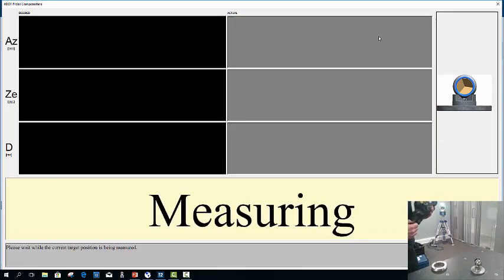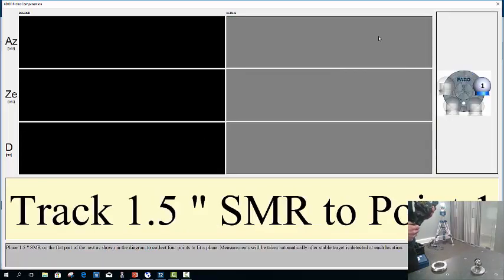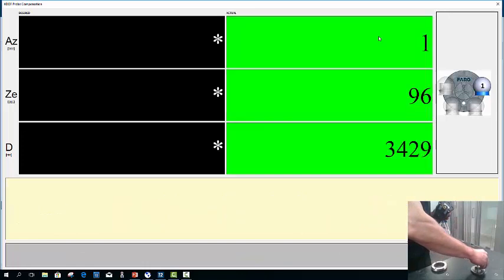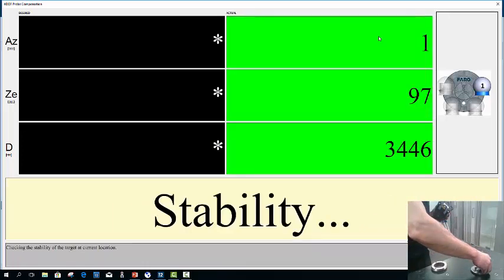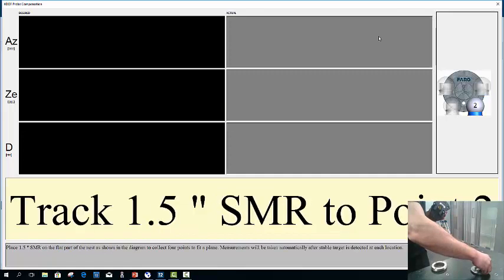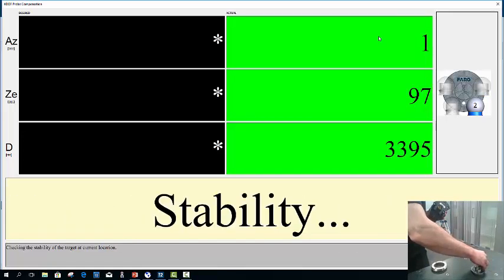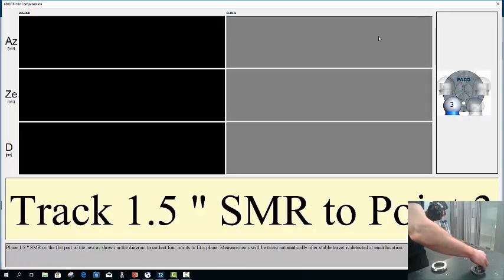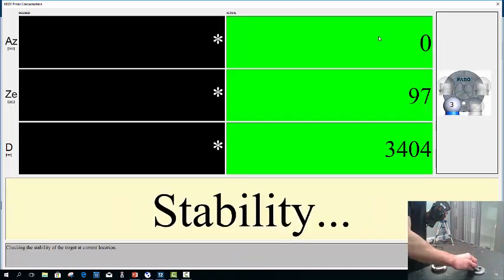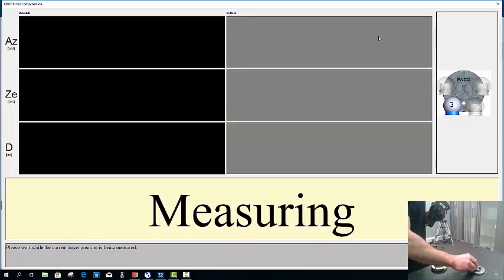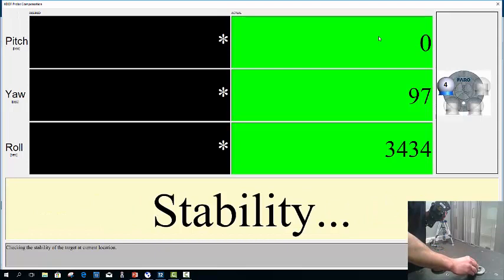With active seek find in the center of the SMR, it will then take the first reading in the center of the artifact. It then will ask you to position the SMR on the base of the artifact to take 4 points around the side. Each time when stability is reached, the laser tracker will automatically take the reading. And the final point, point 4.